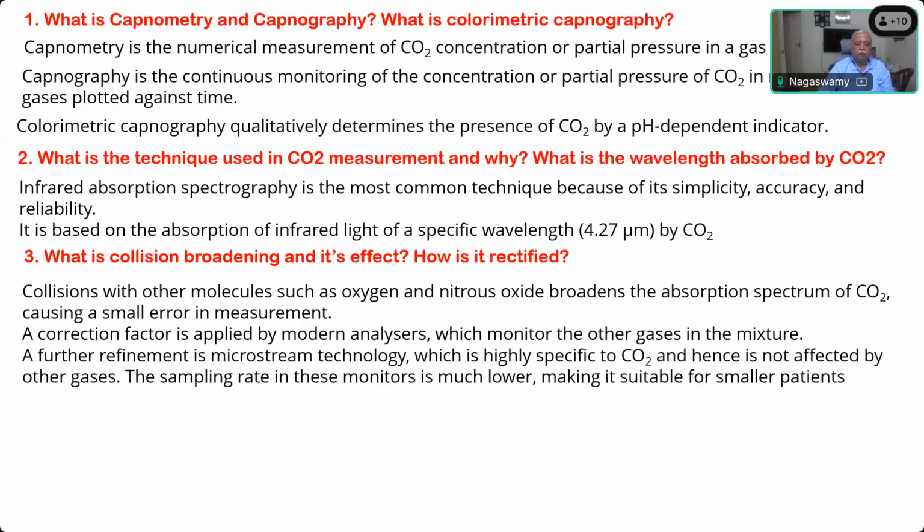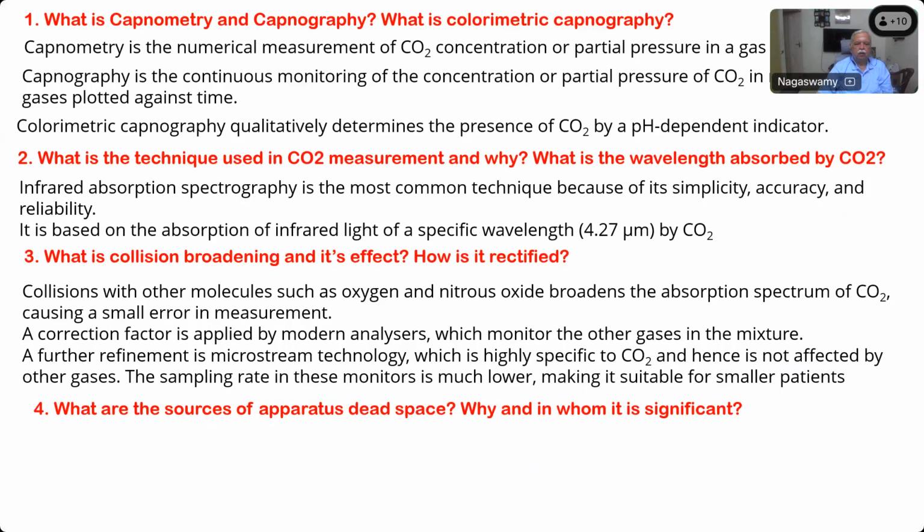The further refinement is microstream technology, which is highly specific to carbon dioxide and not affected by other gases. The sampling rate in these monitors is much lower, making it suitable for smaller patients, especially the pediatric age group. What are the sources of apparatus dead space? Why and for whom is it very significant?